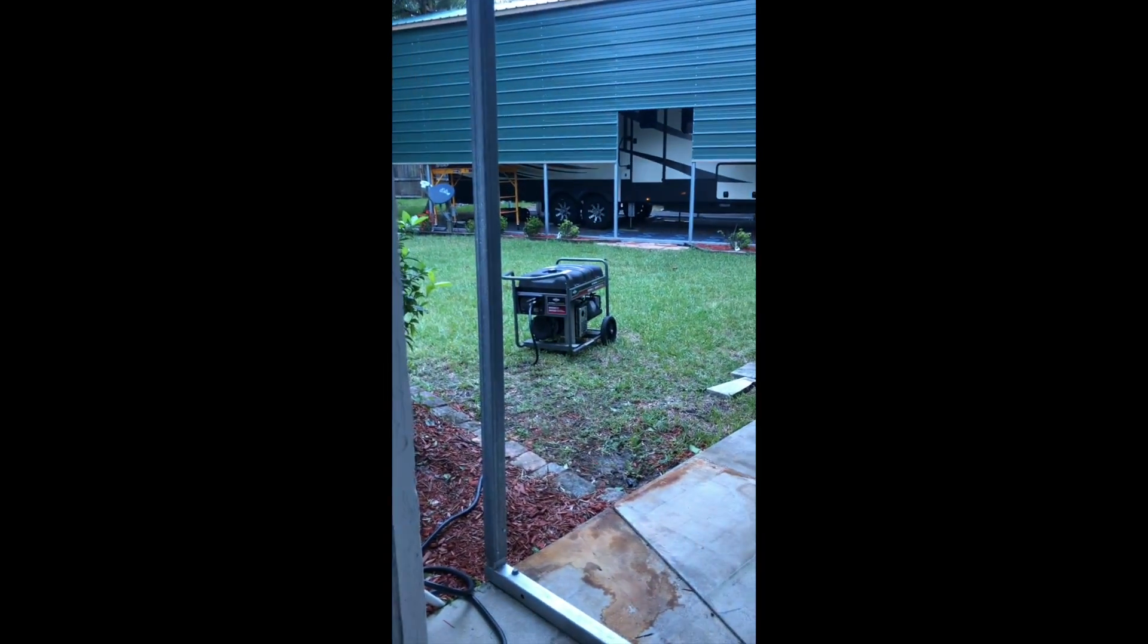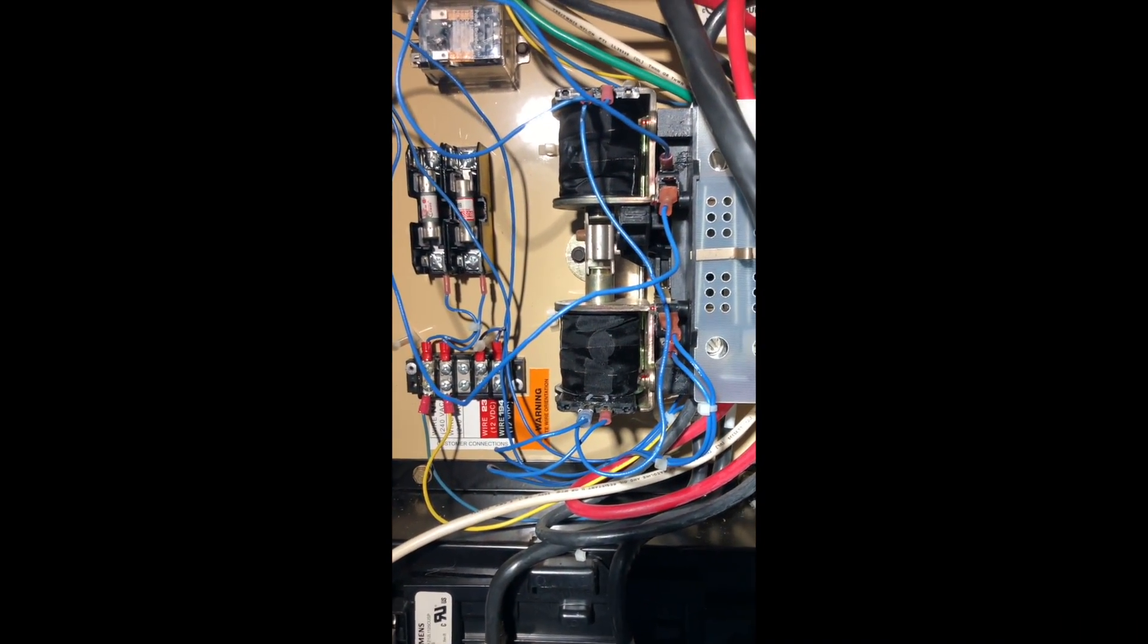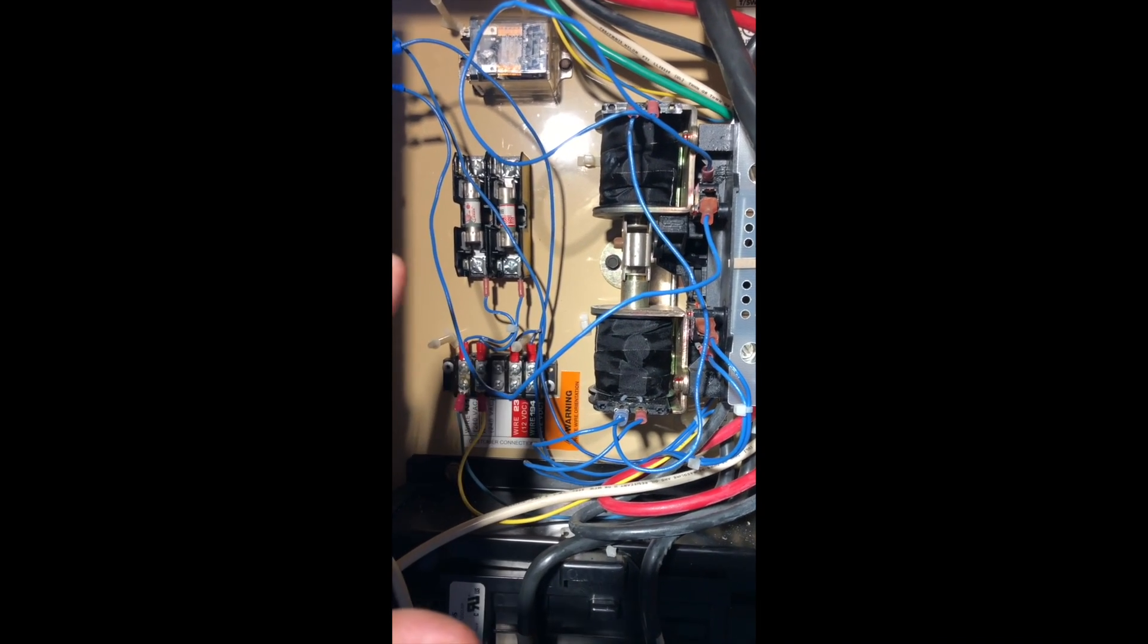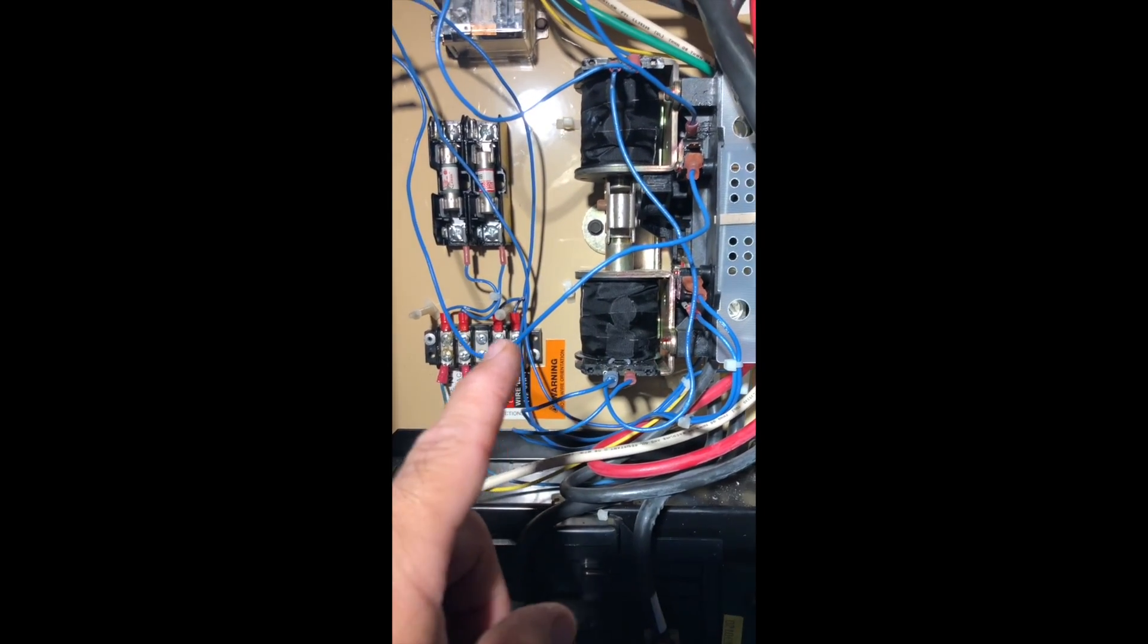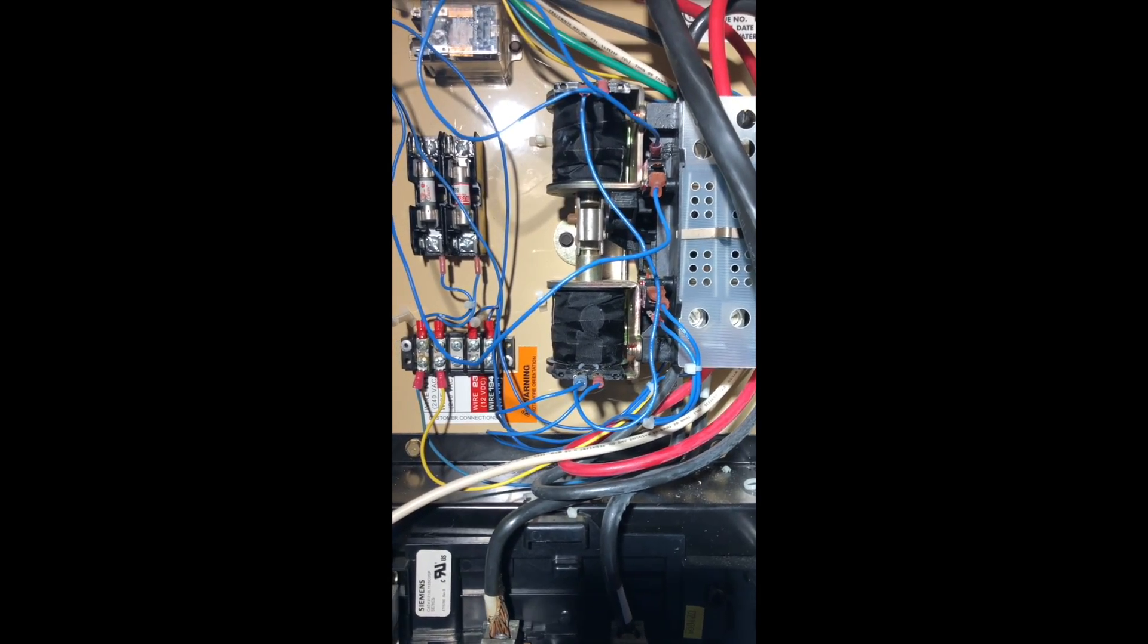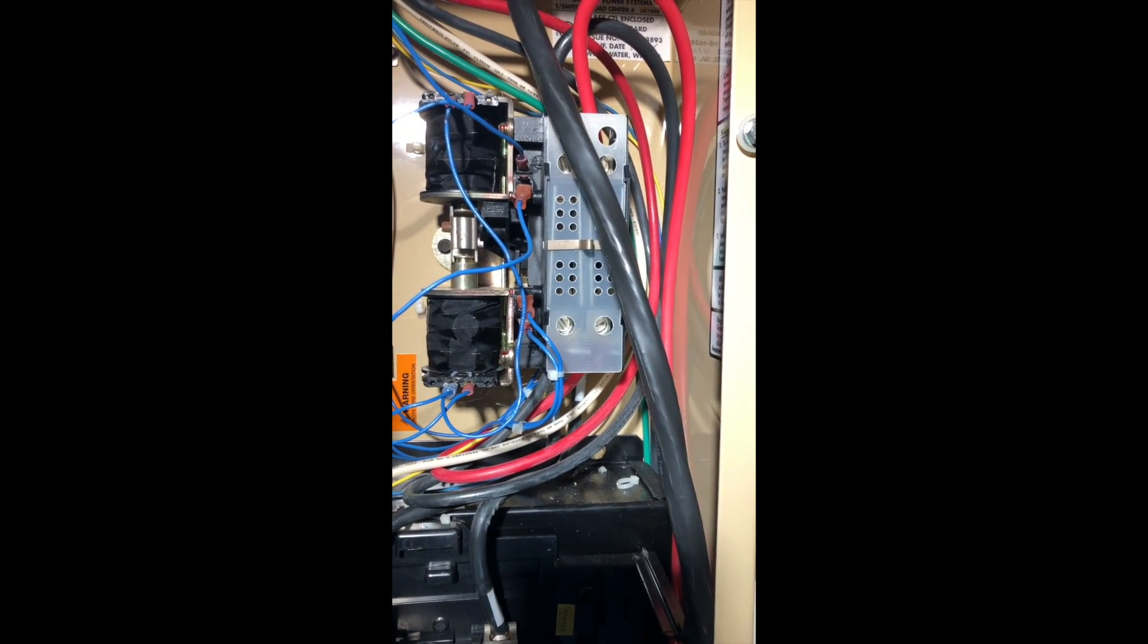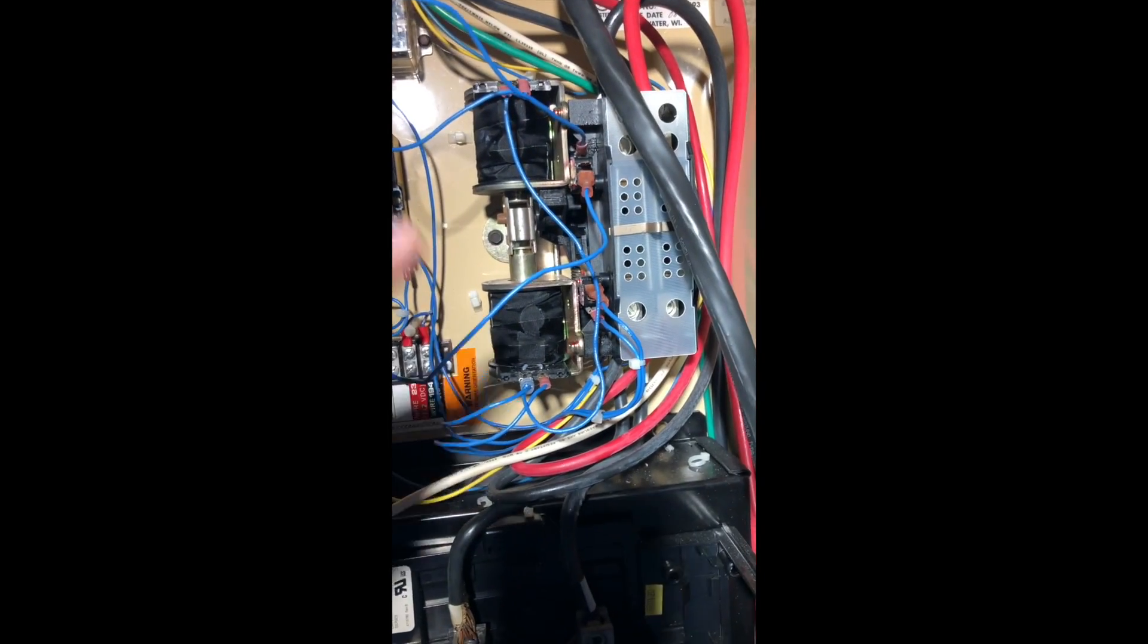What I have now is a standby generator just on wheels that I put an inlet plug into the house, so everything's manual now. I don't mind that because I can get the generator out of the elements, and I can change generator in the future if I want to. But I wanted to keep the function with this, so now in order for the transfer switch to work, I only took power from the bottom, which is the generator side, which means this transfer switch button will only work while the generator is running. If the generator runs out of fuel or becomes inoperable, this will no longer work because it's not going to have power in here anymore. In that case, I could open the case and I could manually flip that down. What I can't do is if the power comes back onto the house, this switch will not work if the generator is not running because the generator supplies power to the transfer switch.